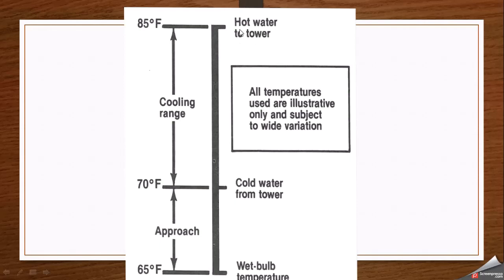Using a typical illustration: hot water enters at 85°F and cold water at 70°F is obtained after passing through the cooling tower. The difference — 85 minus 70 — gives a cooling tower range of 15°F. For approach, if the wet bulb temperature is 65°F and the cold water temperature is 70°F, the difference of 5°F is the approach. As this delta becomes smaller, we get a lesser approach value, and the efficiency of the cooling tower increases.